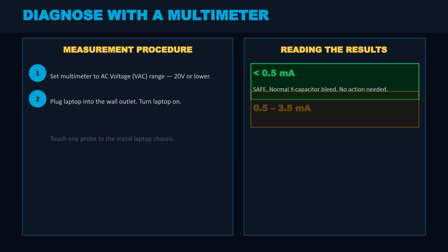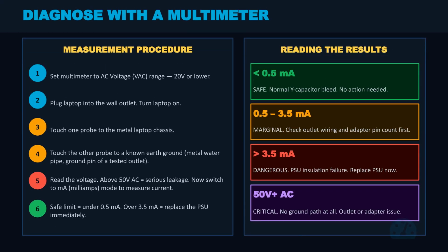Use a multimeter to diagnose the issue. First, check AC voltage. Anything above 50 volts AC means no ground path. Then, switch to milliamps mode. Readings above 3.5 milliamperes are dangerous and indicate PSU insulation failure, requiring immediate replacement.